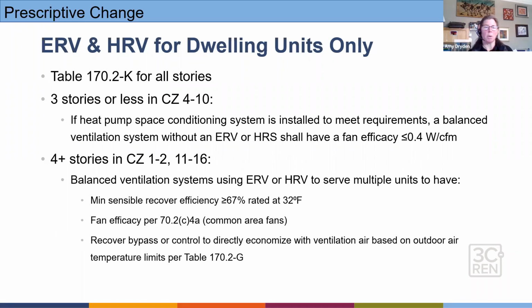For the second bullet point there, 4+ stories in climate zones 1 through 2 and 11 through 16, where I'm utilizing balanced ventilation to meet my ASHRAE 62.2 requirements, and it's serving multiple units, there are performance requirements to ensure we're installing higher performing ERVs or HRVs, because they're going to be operating to provide that whole building mechanical ventilation for multiple units, or that whole home mechanical ventilation. We want it to be higher performing.